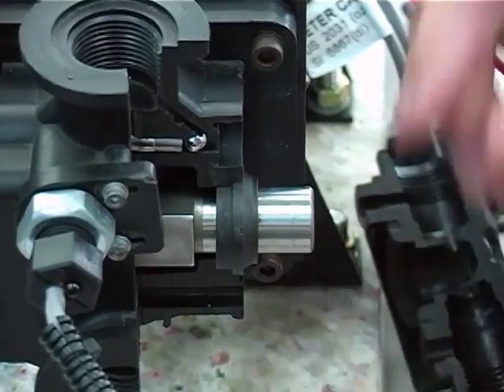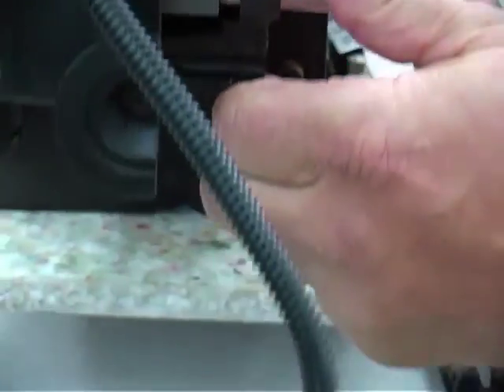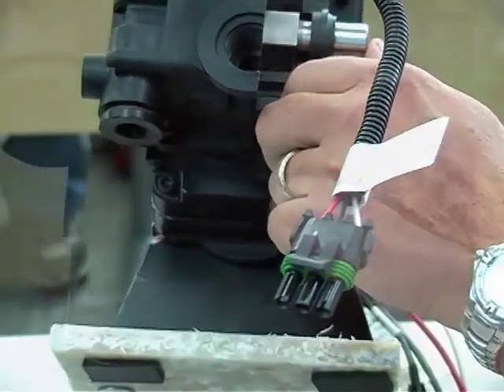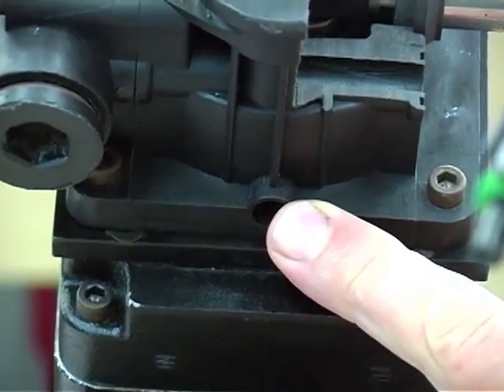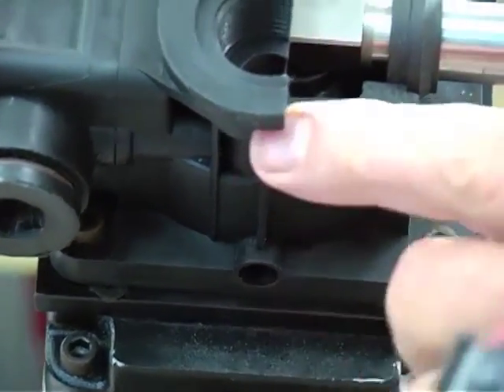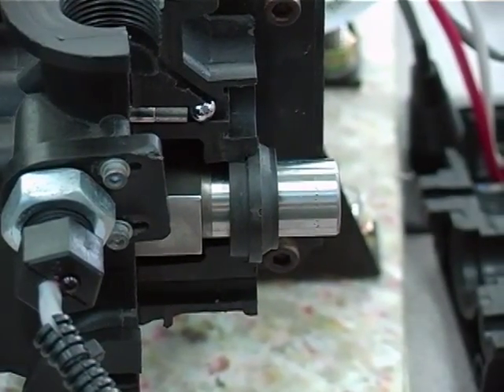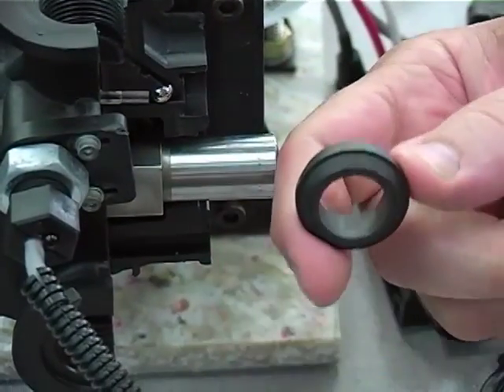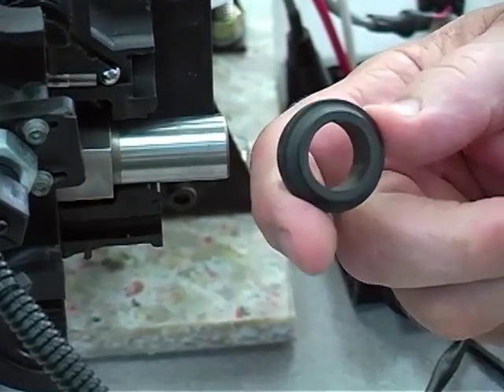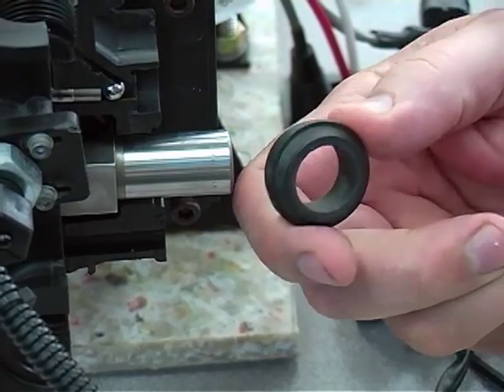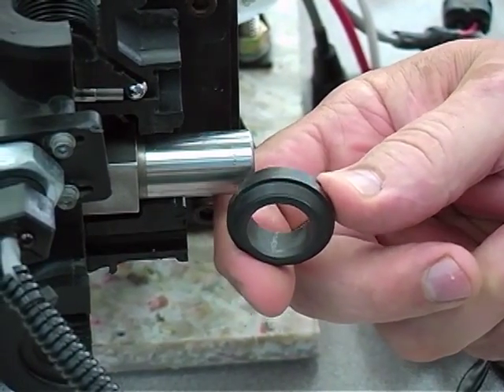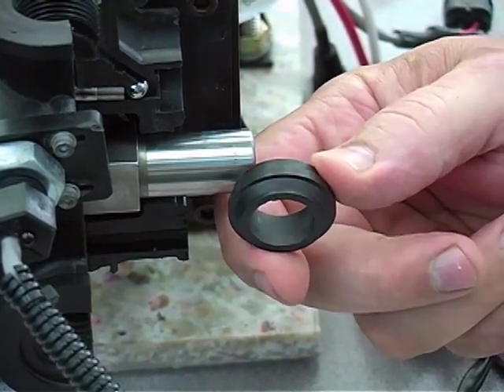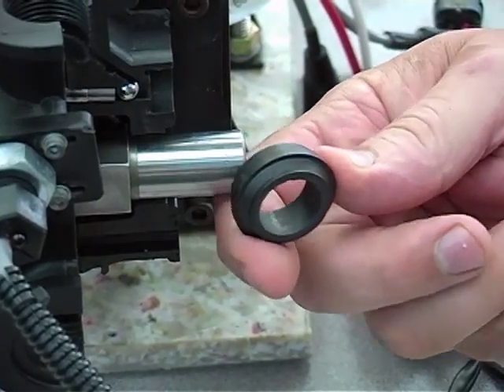If this slipper seal has gone bad, one of the telltale signs is on the underside of the pump. It's called a weep hole. If chemical is getting by on that piston, you're going to get chemical running out the bottom of the weep hole. That'll tell you it's more likely a bad slipper seal. This part here is the bearing, which holds the piston in place. These don't wear out very quick. Because of the type of makeup they are, chemical doesn't bother them. They're a much harder plastic, so we're not going to run into an issue.